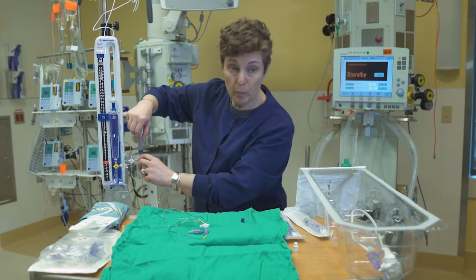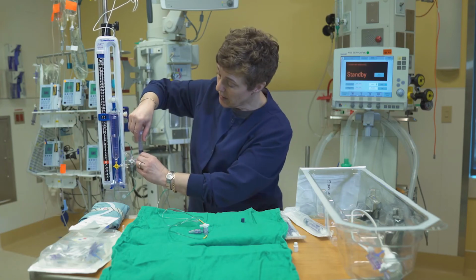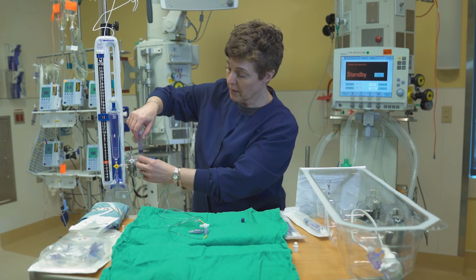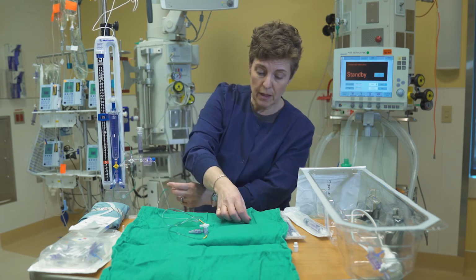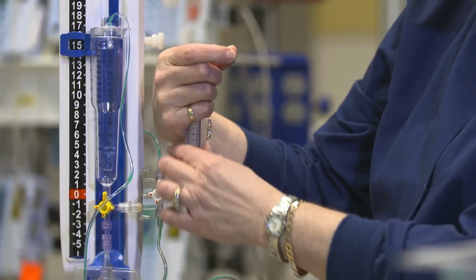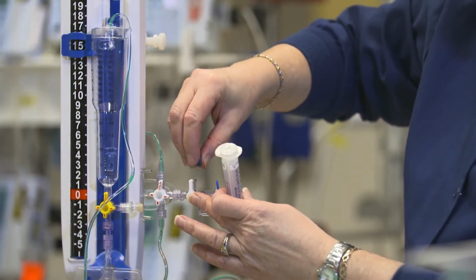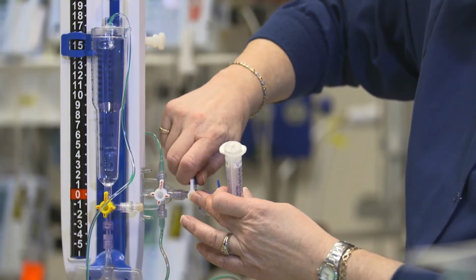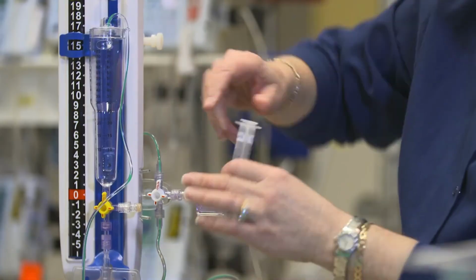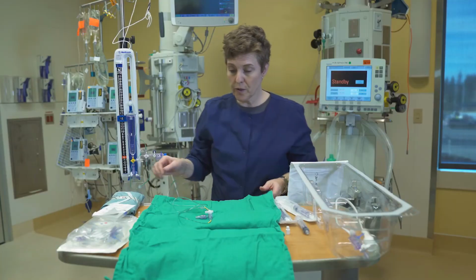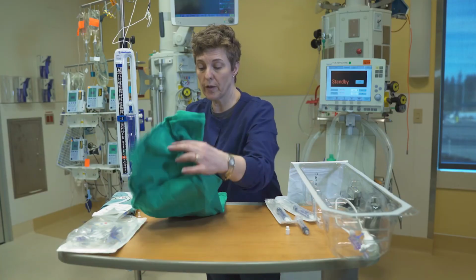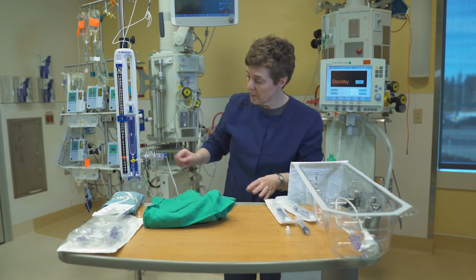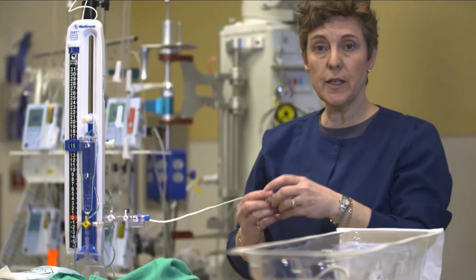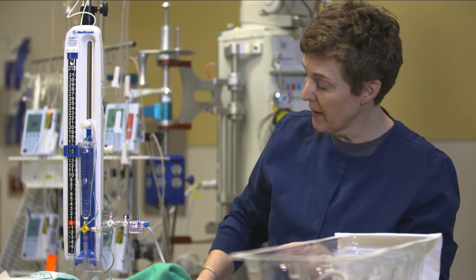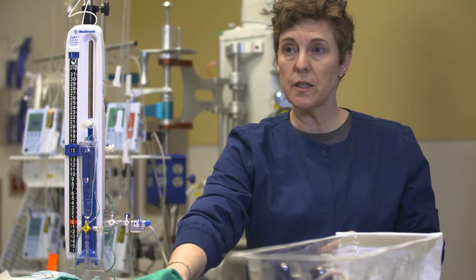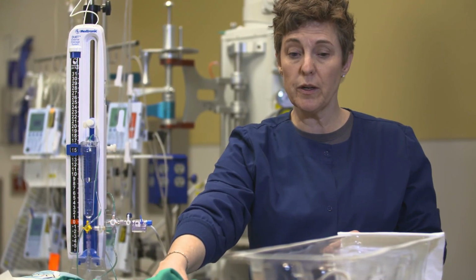Okay, so my last piece that I'm going to do is to close this stopcock. Take my syringe off and replace the cap. I can get rid of this syringe. I'm going to close my huck towel around the end that will be attached to the patient. And you are now ready to plug your pressure cable in and attach this end to the drain that's inserted by your neurosurgeon.